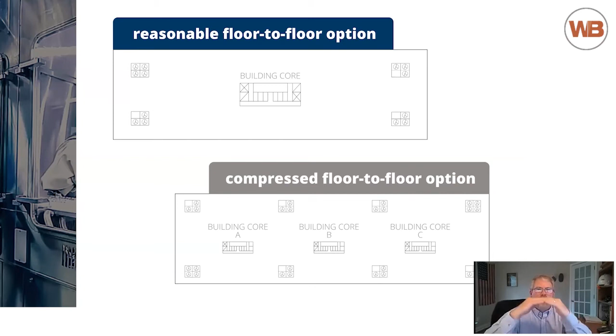When you have a reasonable floor to floor, you just need your supply and potentially return risers, depending on how you're doing it, either mixed single pass or 100% outside air in the central core. Then on that top diagram, you can push those exhaust points to the external corners, so when you bring together your ductwork, you can save floor to floor and manage large ducts without crossing, limiting the amount of bulkhead space you might need.